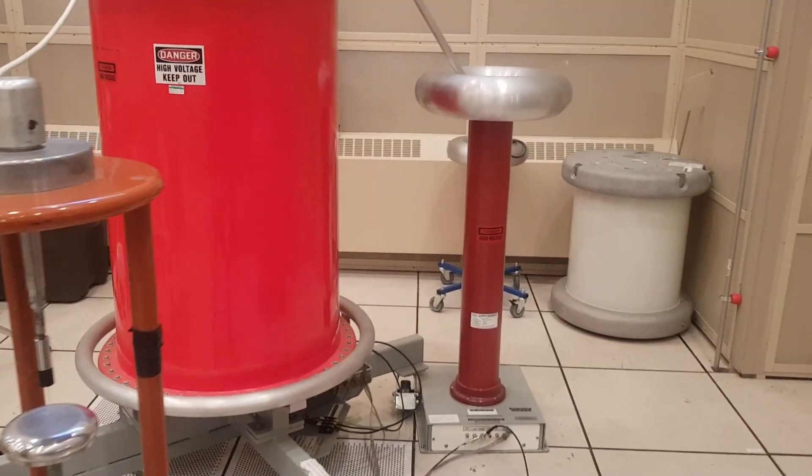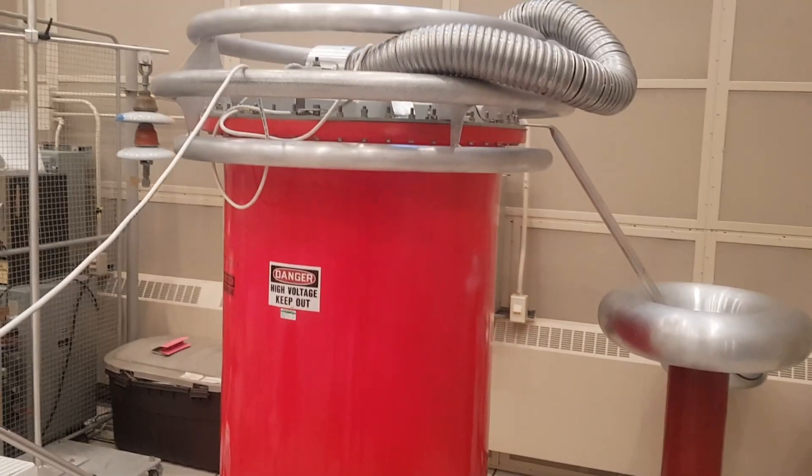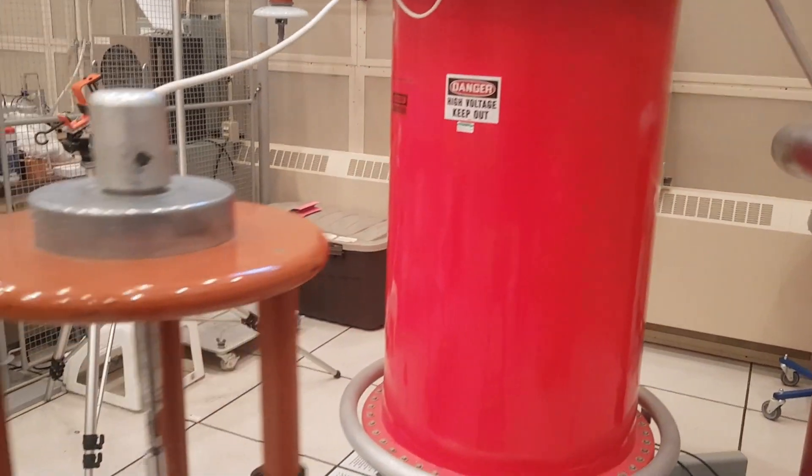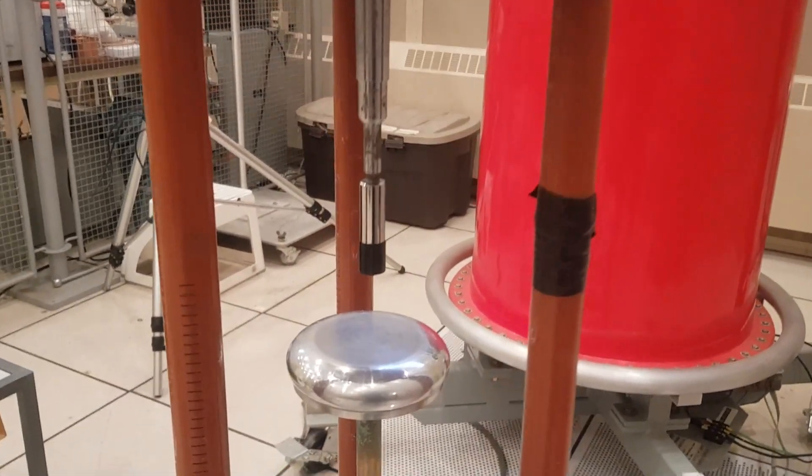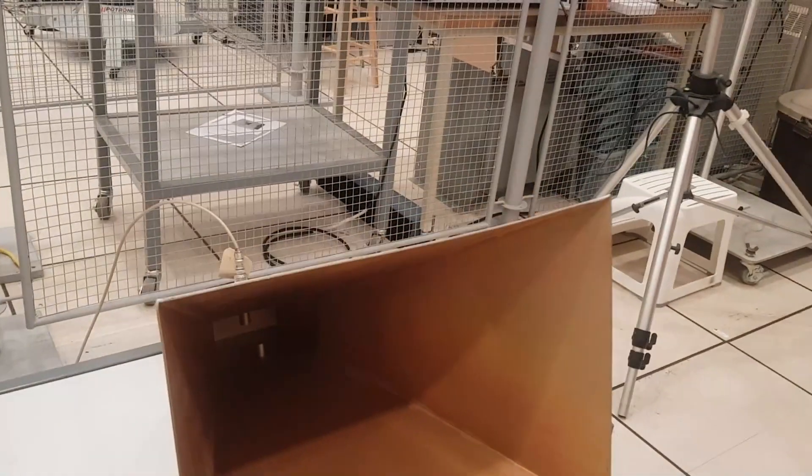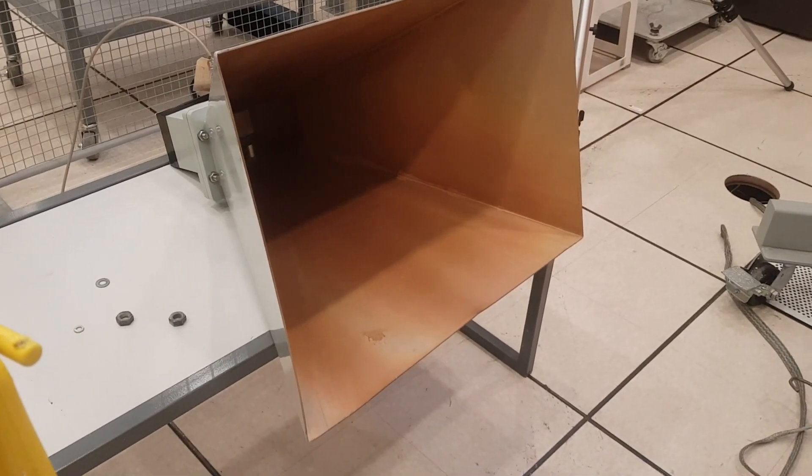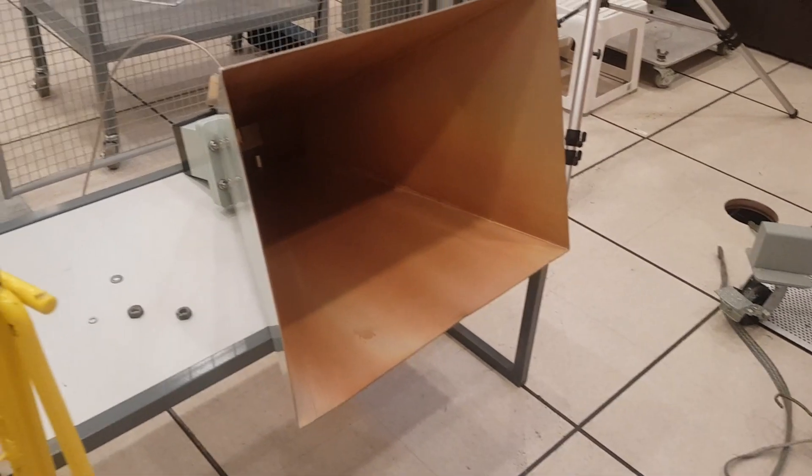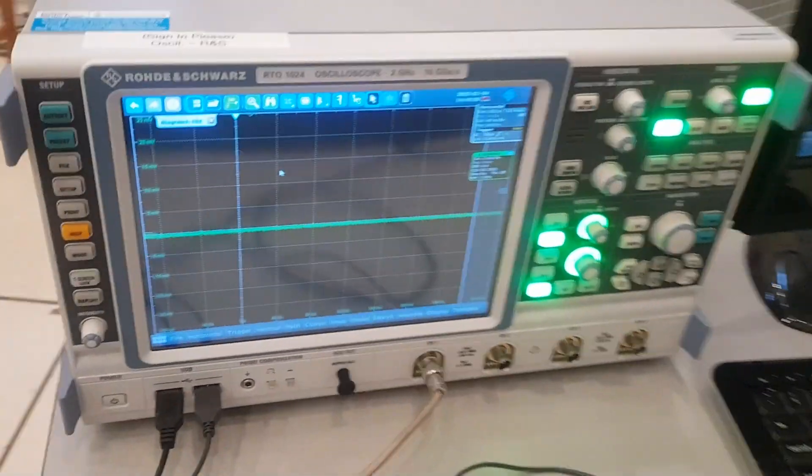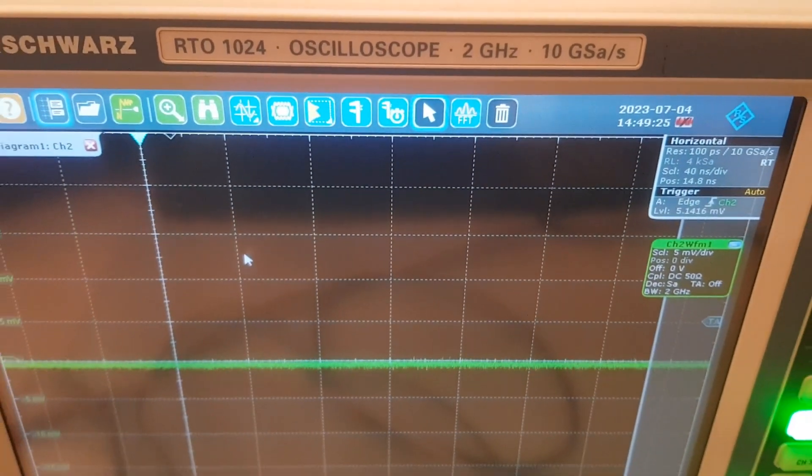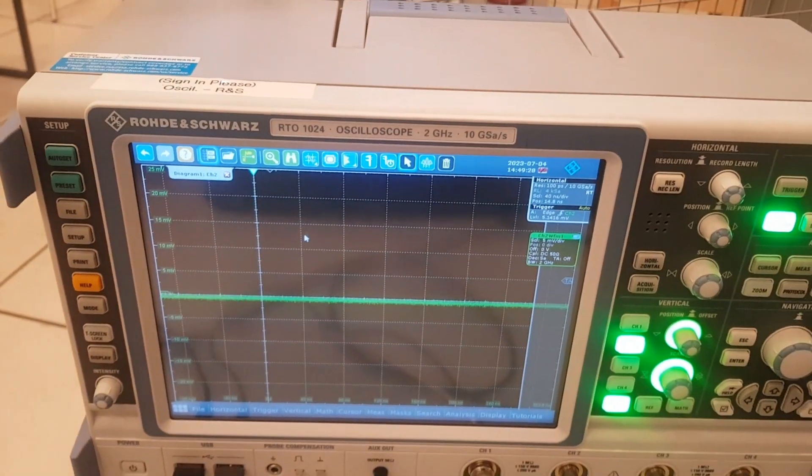This is the partial discharge setup. So here we have the 150 kV transformer connected to this cell, and this cell here connected to a sharp point. And then here we have the RF antenna. It's a directional antenna with a bandwidth between one to two gigahertz. Now the output of the antenna is connected to an oscilloscope with a bandwidth of two gigahertz. So the frequency of the oscilloscope and the antenna are matching.